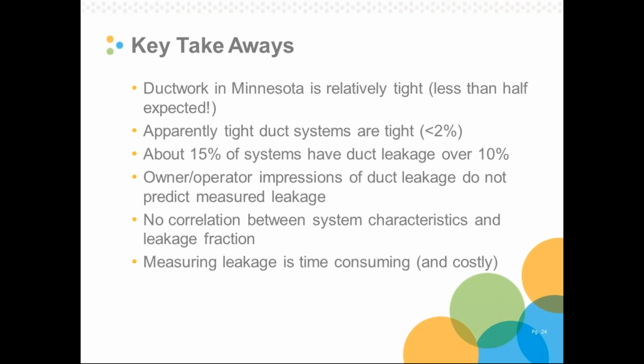We learned a lot of practical things in investigating duct leakage in these buildings. One thing that surprised us was that owner and operator impressions of duct leakage don't necessarily predict leakage. Like most people, it's very easy to notice the big leaks. So when you're an operator walking by a particular duct section and you notice leaks, it's usually because of a leaky access panel or perhaps an unplugged tab port. But again, unless you have access panels every 10 feet and thousands of open tab ports, those leaks are unlikely driving the overall leakage of the system.